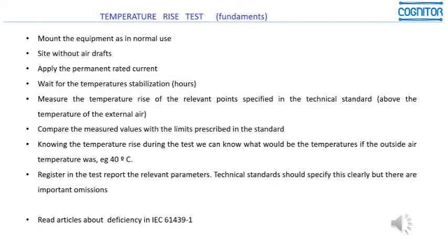Then continue with the temperature rise test, the fundamentals. We mount the equipment as in normal use in a site without air drafts. You cannot do a test inside a room with open doors where the air will flow, because these have a very high influence on the temperatures which will be measured in the parts. We shall apply the permanent rated currents, wait for the temperature stabilization, and this takes hours.